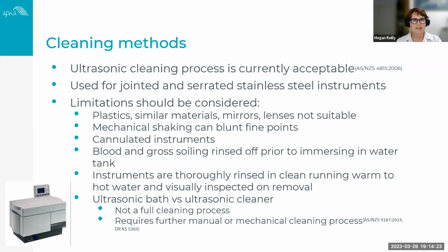So when I talk about ultrasonics, I often talk about ultrasonic baths versus ultrasonic cleaners. Now, an ultrasonic bath is really not a full cleaning process, because if you think about it, you put your instruments into the basket, you switch it on, you remove them, you rinse them, then you put the next load of instruments into that bath. It's a bit like a family that has a group of children, and the first person who gets in the bath actually gets washed and comes out clean, but the subsequent kids that get in the bath, in actual fact, are being cleaned in dirty water as such. And an ultrasonic bath is very similar to that. So it's not a full cleaning process where we empty it out after each use.